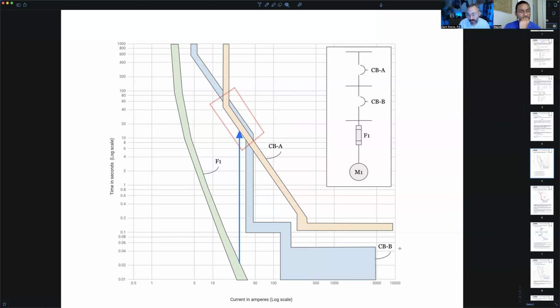We would want just circuit breaker B to trip. But right now, circuit breaker A is going to start to unlatch first, and we could also end up tripping circuit breaker B right around here if it's not fully cleared by A. So really all we're looking to do is figure out how to get rid of this overlap. How do we get it so it's not overlapped?